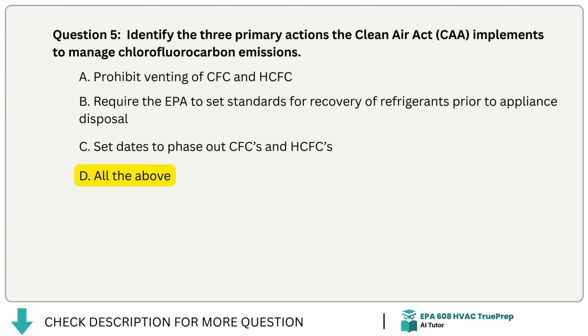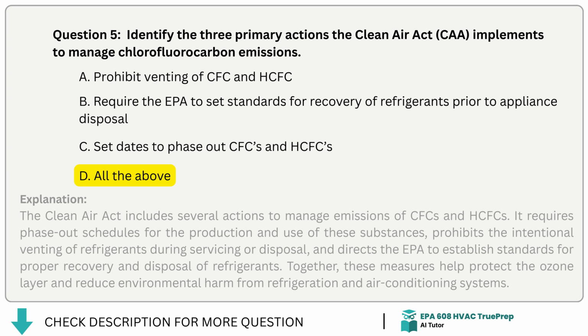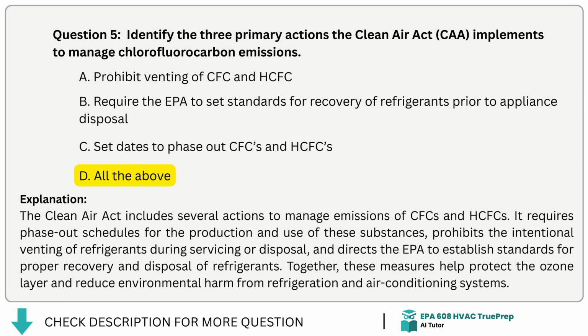All the above. The Clean Air Act includes several actions to manage emissions of CFCs and HCFCs. It requires phase-out schedules for the production and use of these substances, prohibits the intentional venting of refrigerants during servicing or disposal, and directs the EPA to establish standards for proper recovery and disposal of refrigerants. Together, these measures help protect the ozone layer and reduce environmental harm from refrigeration and air conditioning systems.